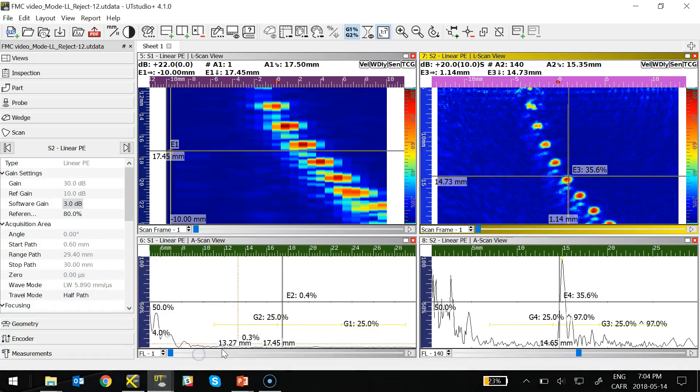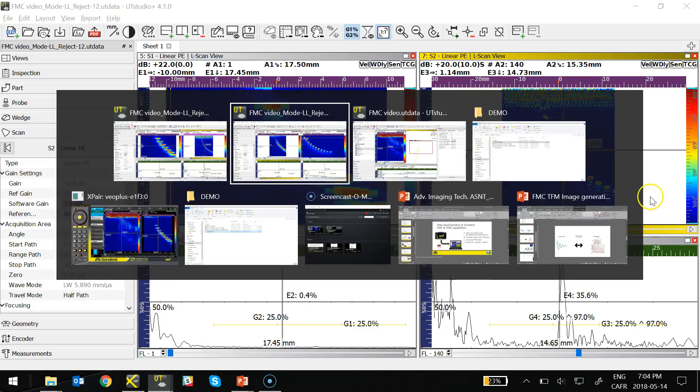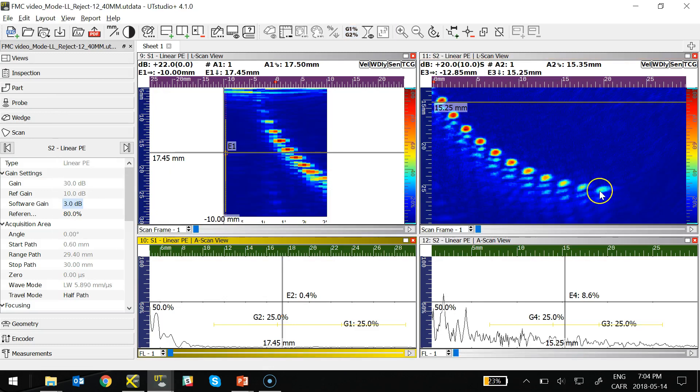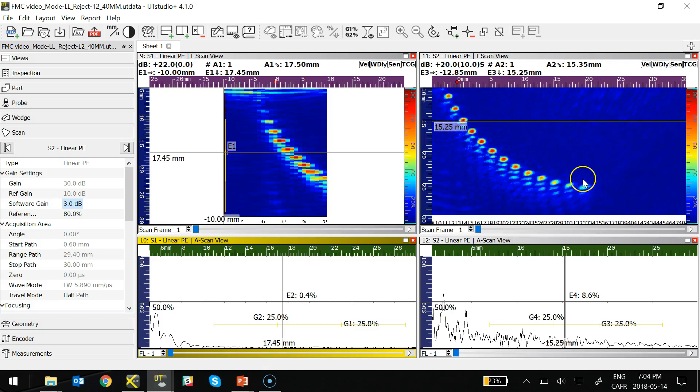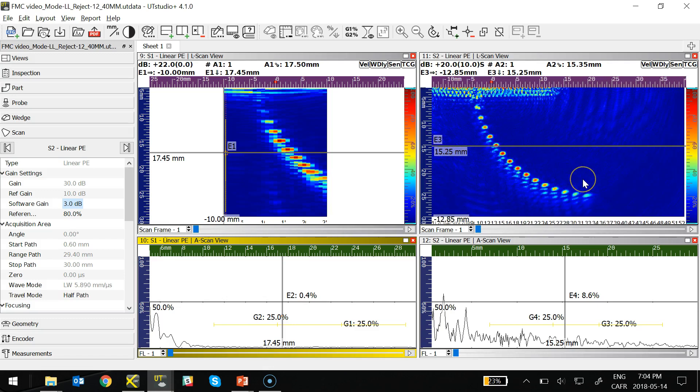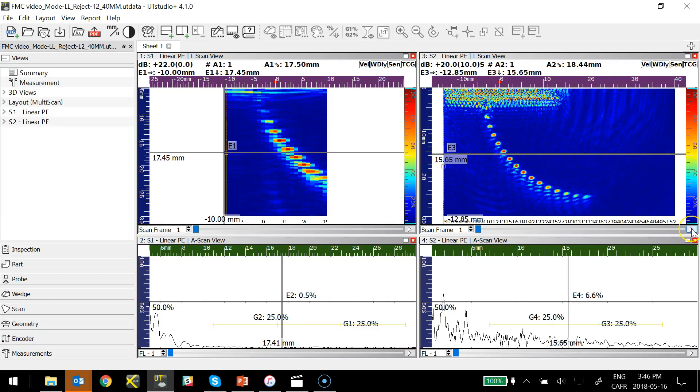So if I compare with the other TFM scan or dataset that I created the first time, we clearly see that we missed some defects in this zone, while by recomputing a new extended TFM zone, we see that we now include all the defects into the analysis area.